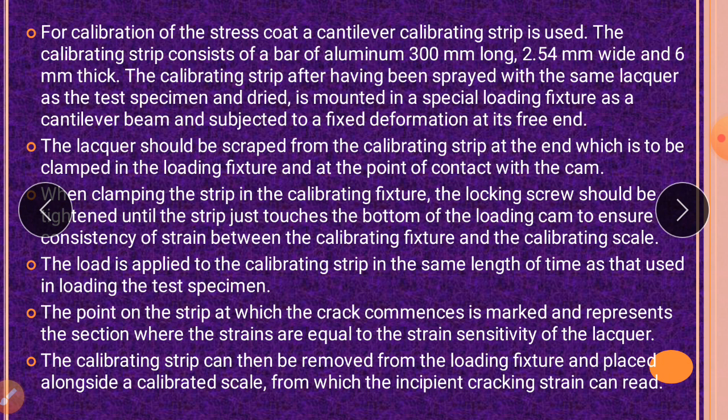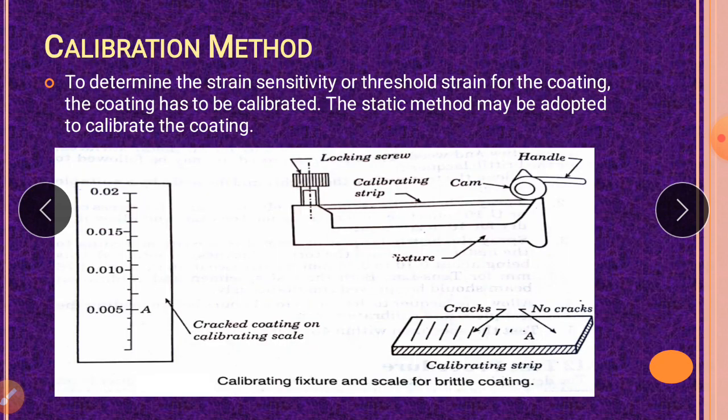Thank you students. I hope you have understood this method of calibration. You have to use one special fixture. One end is fixed, one end is free. By using a cam handle, you apply the load. The strip is going to be bent. It will act as a cantilever beam.